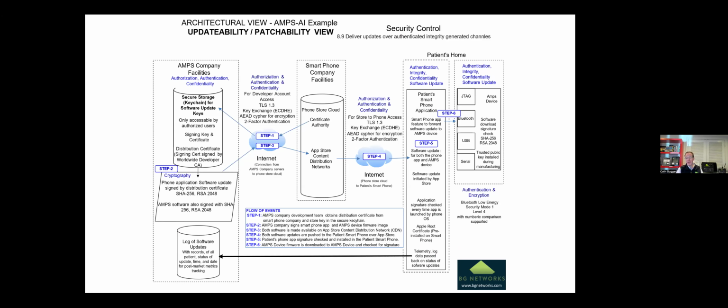And for your cybersecurity plan, the FDA is expecting that you'll keep metrics of how quickly you can update devices and what percentage of devices are being updated. And you're going to want to ideally do this in an automated way. And this would be a way of doing that, which is keeping a log of which devices actually received the software updates.